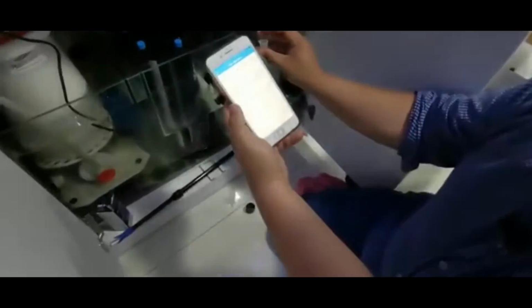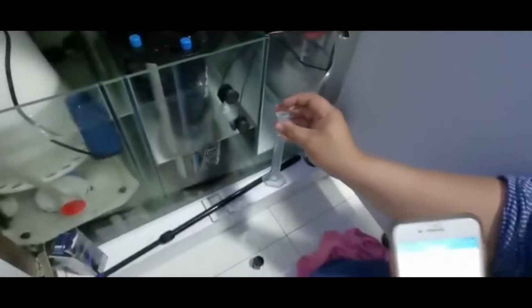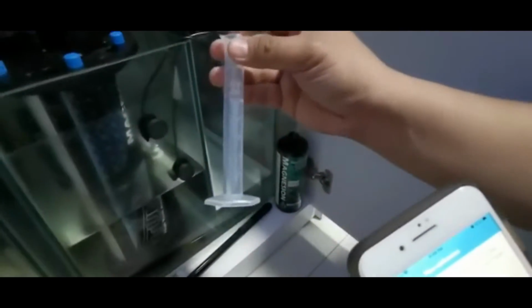To calibrate, we go to the second option, which says insert the outlet through the connecting tube into an empty cylinder and click the digital input for titration, 10 seconds. Place the other outlet and tube into the measuring cylinder and click start. So I have one tube in the magnesium bottle, and the other outlet in the calibration cylinder. I'll hit start, and it will run for 10 seconds.